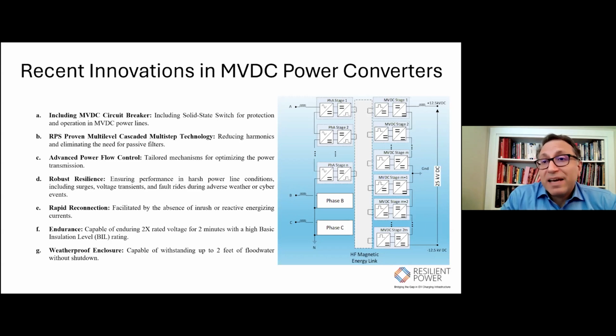The technology that we have also includes an MVDC circuit breaker, which, as we know, is very difficult to get hold of, especially at MVDC. So we have a solid state switch that can act as protection and also as energization. These kinds of power converters don't have any inrush current. We know transformers have inrush current, but the MVDC power converters, the resilient version, don't have any inrush current.